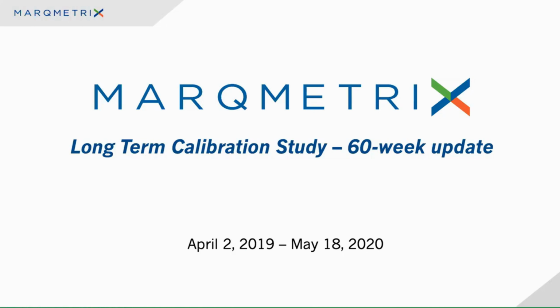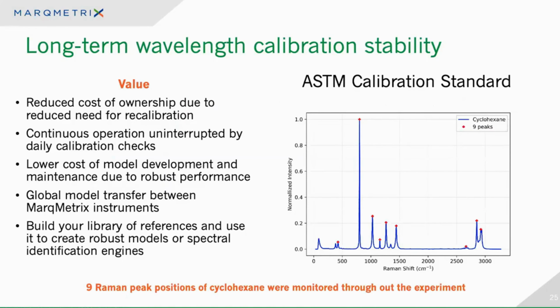This box was built about 18 months ago. It was only calibrated when it was built, and it's never been calibrated since. Why do we find long-term wavelength calibration stability important? Primarily, it reduces the cost of ownership due to the reduced need for recalibration. Continuous operation uninterrupted by daily calibration checks provides value. It's a lower cost of model development and maintenance due to robust performance.